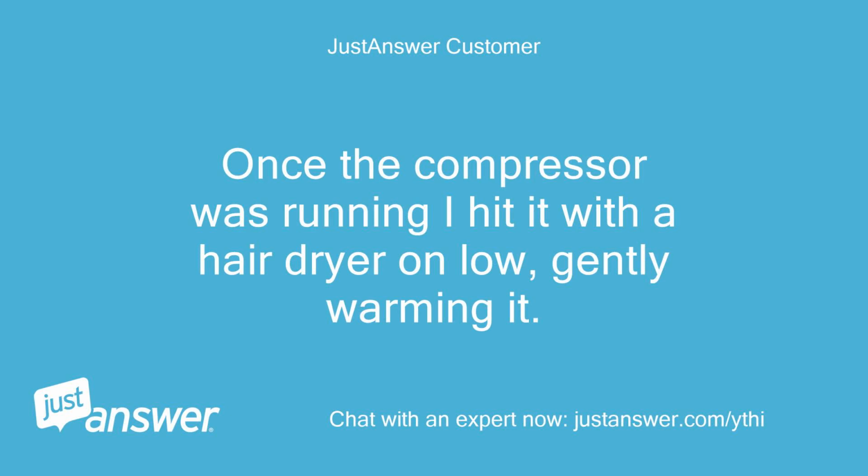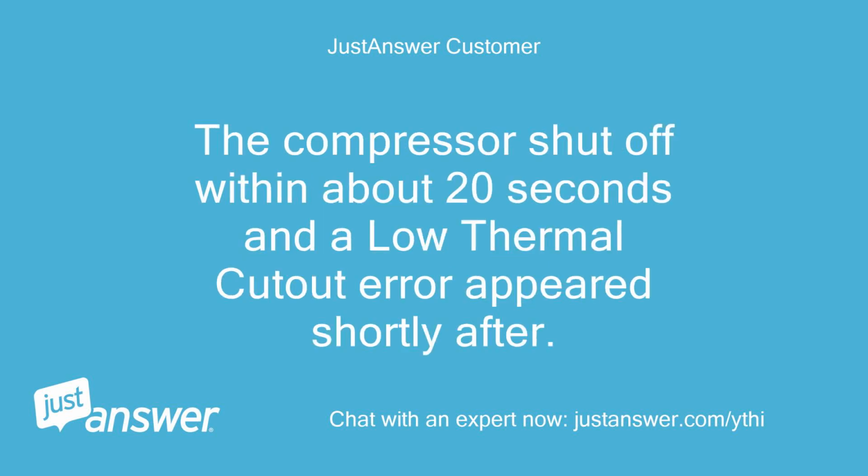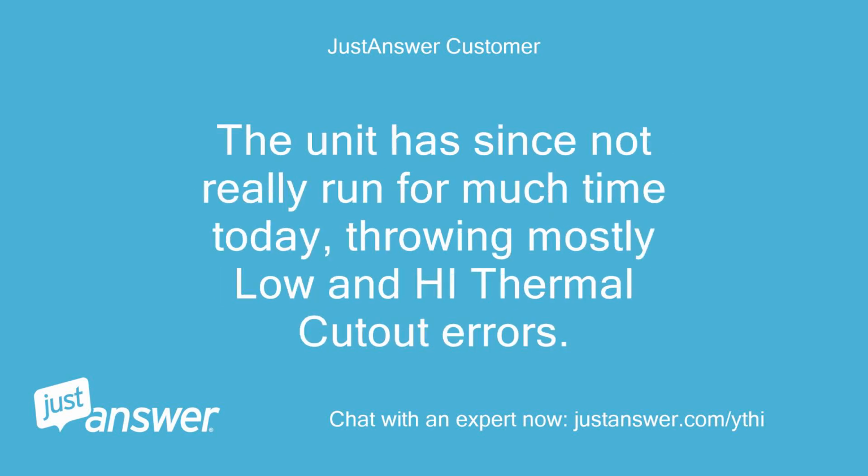Once the compressor was running, I hit it with a hair dryer on low, gently warming it. The compressor shut off within about 20 seconds and a low thermal cutout error appeared shortly after. The unit has since not really run for much time today, throwing mostly low and high thermal cutout errors.